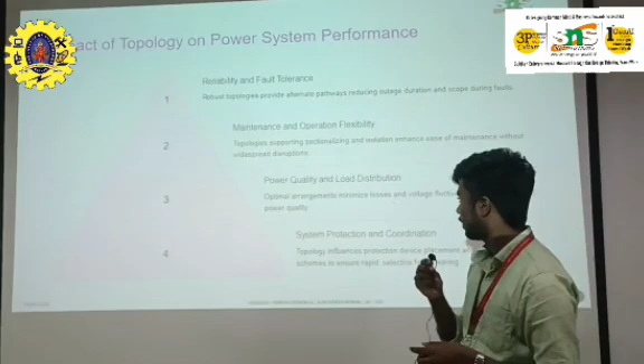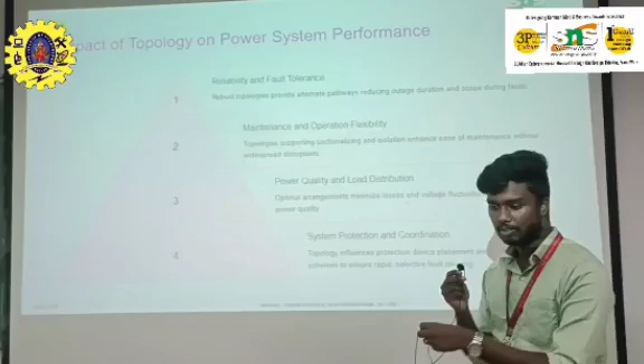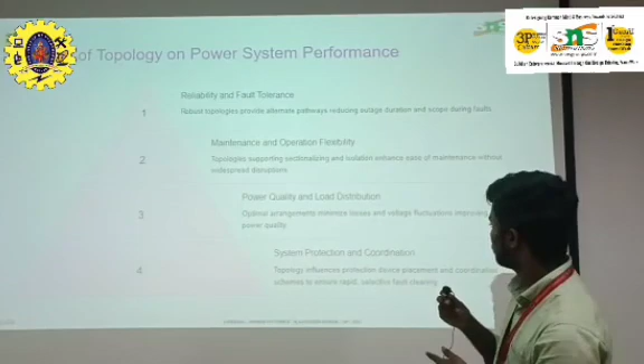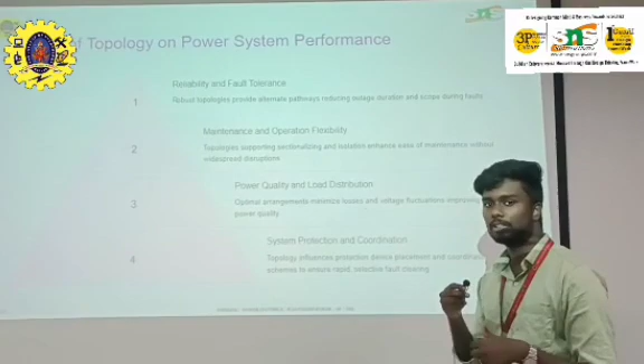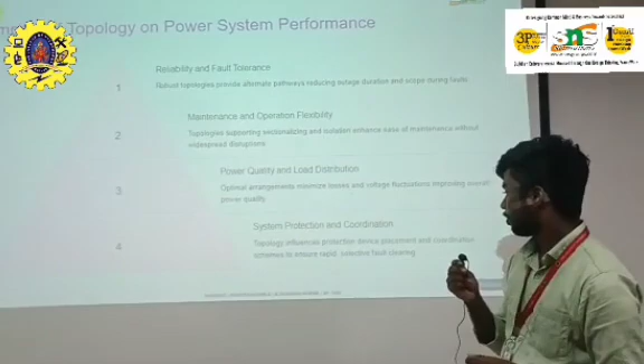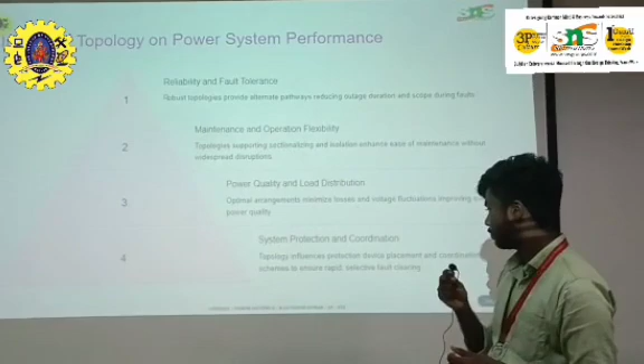The third point is power quality and load distribution. As the different nodes are connected with different structures, the optimal arrangement minimizes the loss and voltage fluctuation. So it improves the power quality overall. The last point is system protection and coordination. Topology influences protection device placement and coordination schemes to ensure rapid selective fault clearing.